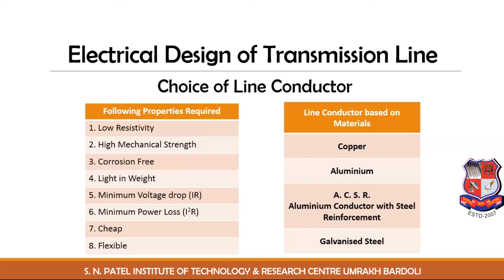The last topic of the session is spacing between conductors. We use an empirical formula to find the spacing between the conductors. The spacing is equal to square root of (d plus V by 150) in meters, where d is the sag in meters at 40 degrees Celsius, and V is the voltage in kV. The spacing arrangement may be horizontal, vertical, or equitriangular.